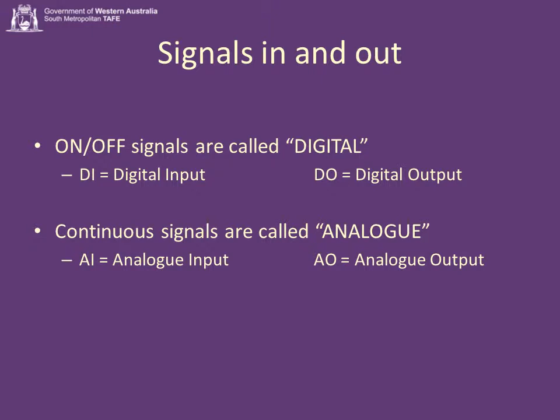Continuous signals, such as temperatures, which can be anything from 0 to 100 degrees Celsius, or flows, which can be 0 to 200 litres a minute, or pressures, which can be 0 to 400 pascals. Things that are continuous, we call those analog - that's a historical thing. So continuous signals coming in, we call analog input, AI. And continuous signals going out, we call analog output, AO.